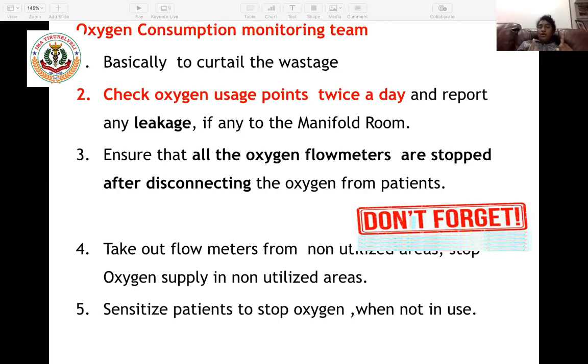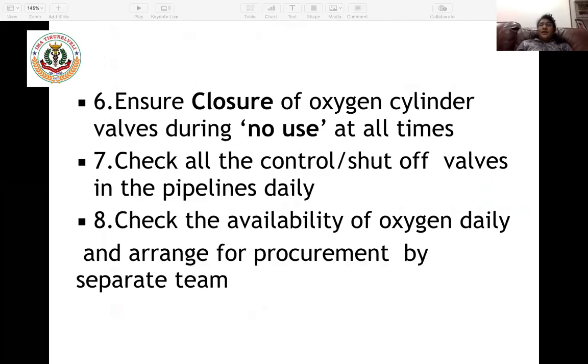Don't forget to take out all the flow meters from the non-utilized areas, stop oxygen supply in non-utilized areas, sensitize the patients to stop oxygen when not in use, and ensure closure of oxygen cylinders and valves when not in use at all times. Check all the control and shut off valves in pipelines daily. Check the availability of oxygen daily and arrange for procurement by the special team in the hospital.